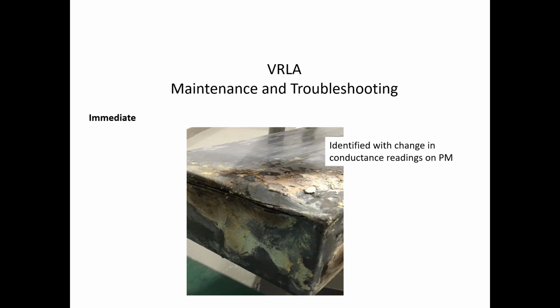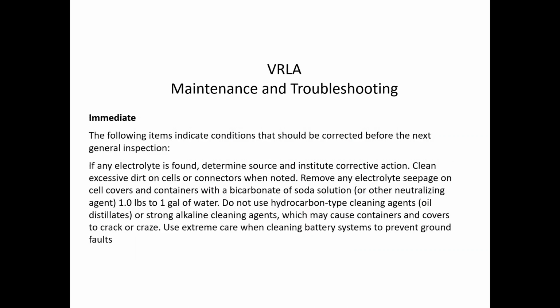So with ohmics and float current of the battery, we found there's a suspect cell here. Further investigation pulled it out, and again, that's something you would never see looking at the front of that battery. It looked perfectly fine. Not a single indication that there was a potential issue with the battery. But that's where those conductance and impedance readings come in handy.